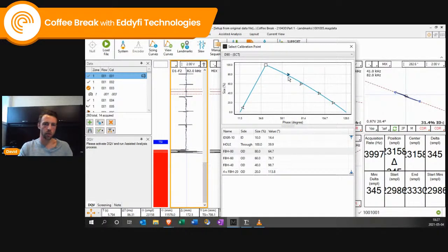So you have a few things you can play with. You can play with your frequency. You can reassign the values, rescan your tubes, and make sure you rebalance also. So just restart the calibration process a little bit. That can happen. And sometimes these are vector measurements, so sometimes the computer misinterprets the angle from a 180-degree difference. Sometimes we just need to redo the calibration, and it's going to pick it up.